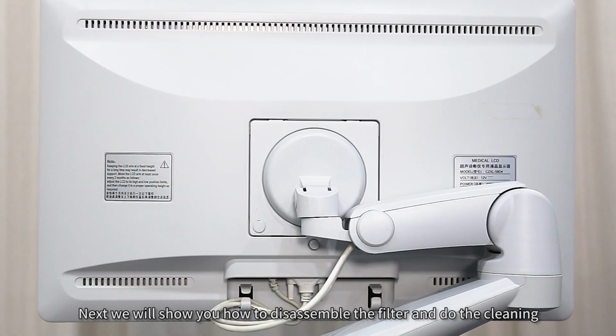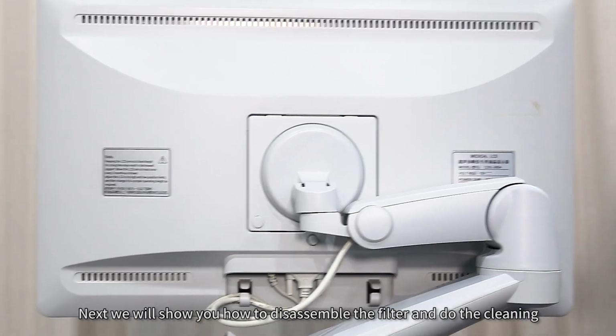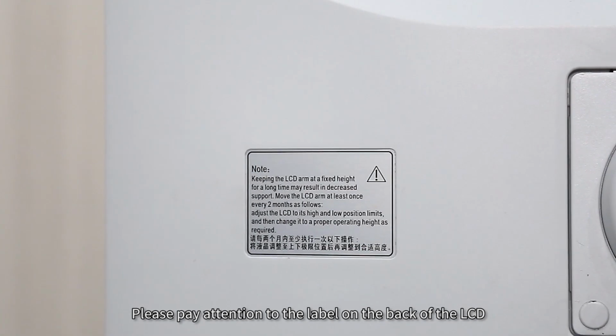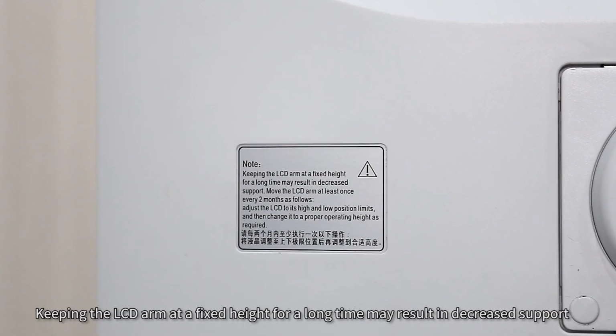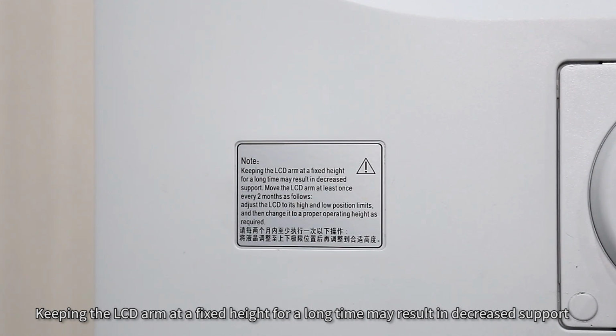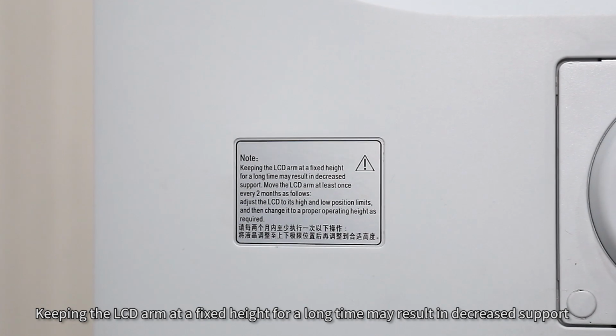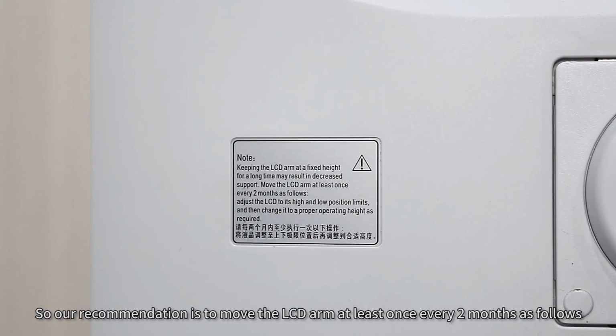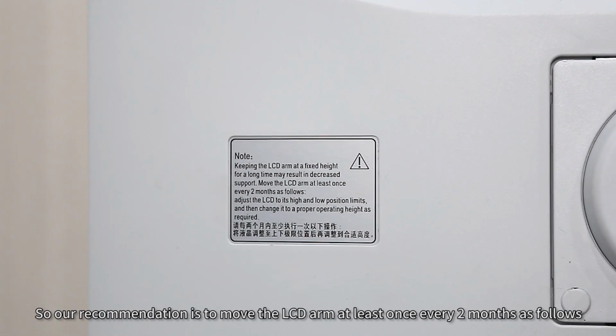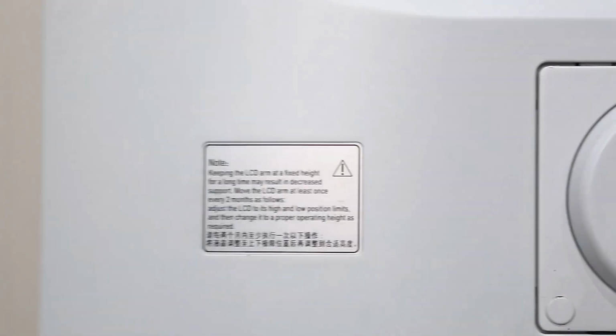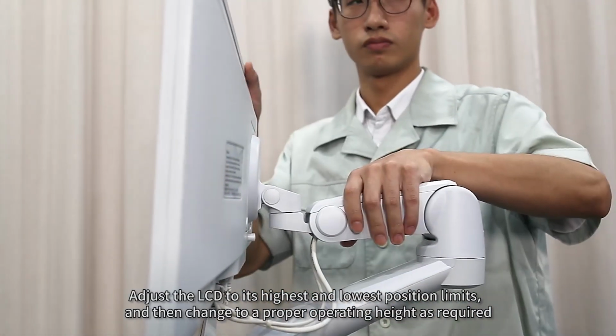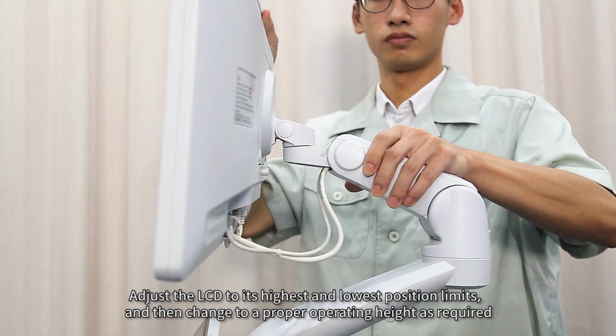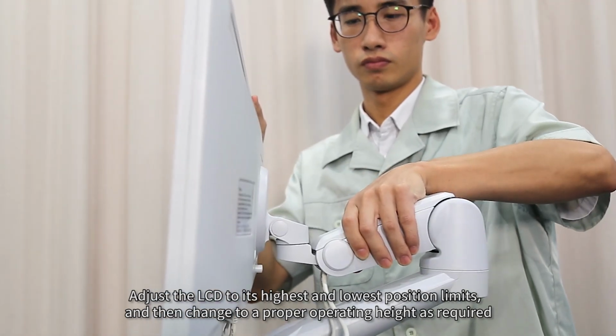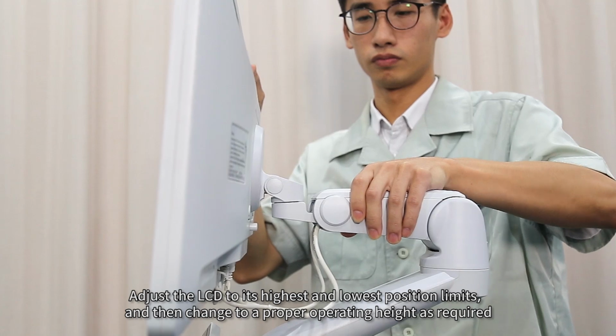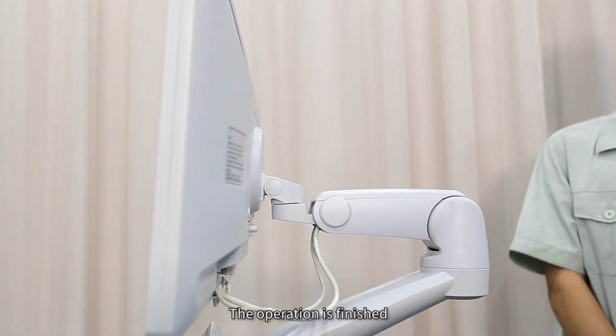Now we will present you the daily maintenance of the gas spring. Please pay attention to the label on the back of the LCD. Keeping the LCD arm at a fixed height for a long time may result in decreased support. So our recommendation is to move the LCD arm at least once for every 2 months as below. Adjust the LCD to its high and low position limit, and then change it to a proper operating height as required. The operation is finished.